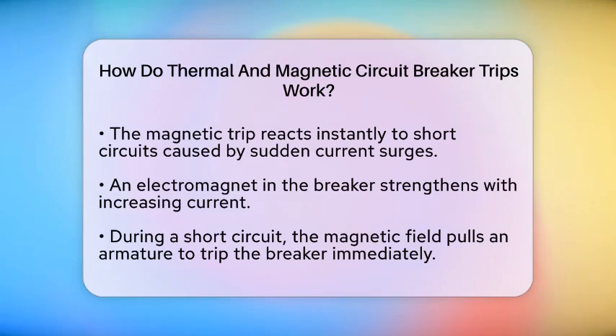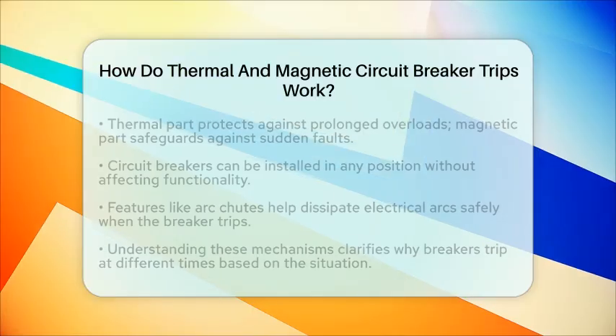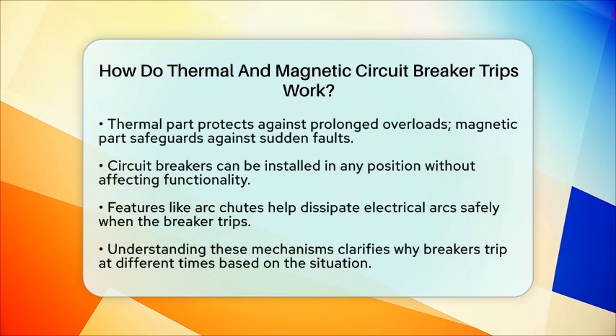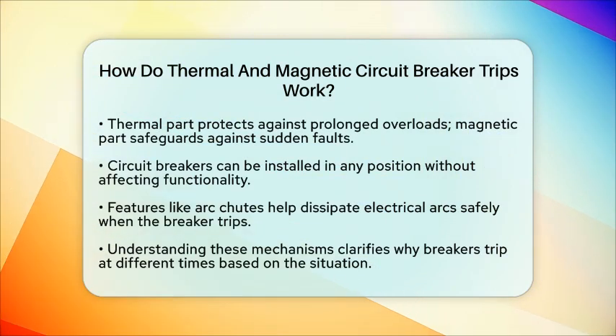In practical terms, if you have too many devices running on one circuit and the current rises slowly, the thermal part will trip the breaker after some time. But if there is a sudden fault, like a wire touching another wire, the magnetic part will trip the breaker instantly to prevent hazards.